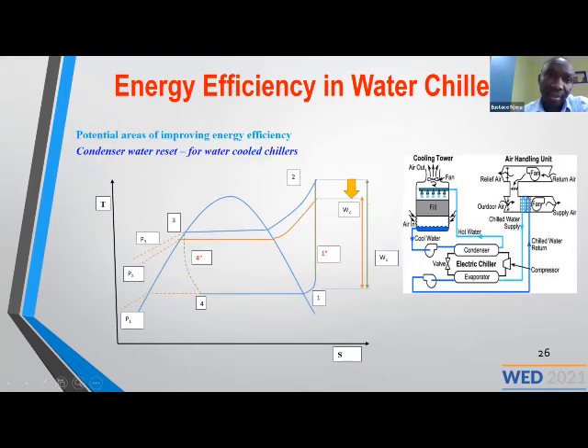The other one is the condenser reset. Instead of operating at temperatures which are very high, you can reduce the temperatures. If you monitor the external temperatures, especially if you are using a cooling tower, you can reset, so that if the water temperature reaches a certain point, you can switch off the compressor. And in such a case, you save a lot of energy.